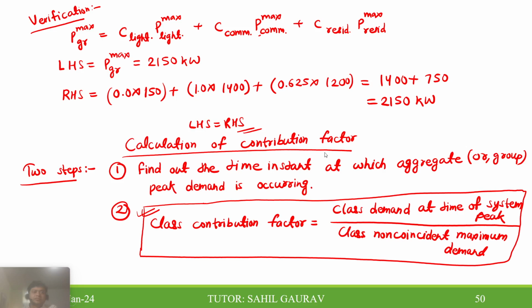For the calculation of the contribution factor, I have written down the steps. The first step is to find the time instant at which the aggregate peak demand is occurring. If you find the time instant, that's okay; it has no other relation with the group peak demand. Now for the class contribution factor, in the numerator you put whatever demand is occurring during that group peak instant, divided by the individual peak demand of that class. In that way you can calculate the contribution factor from the table given.